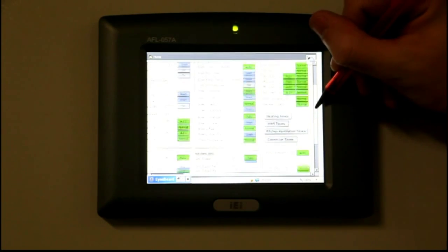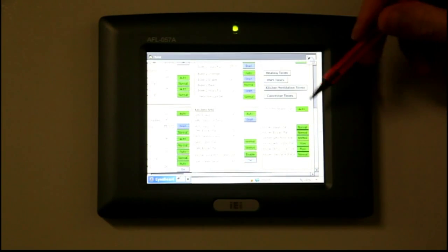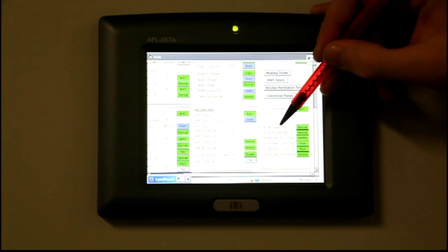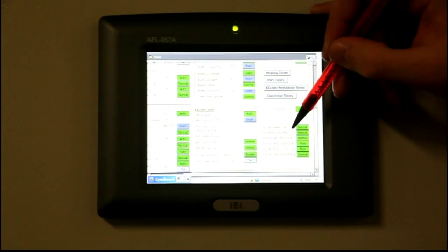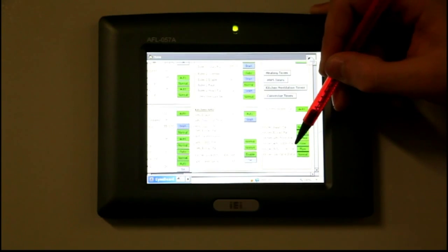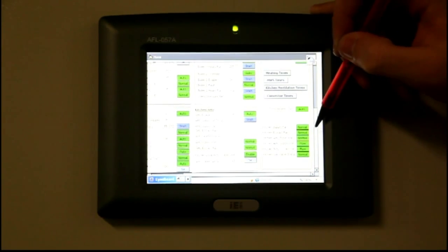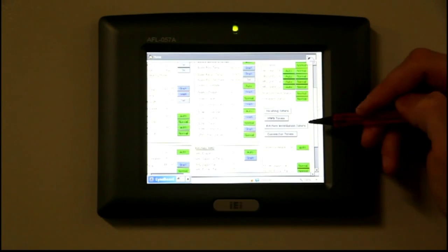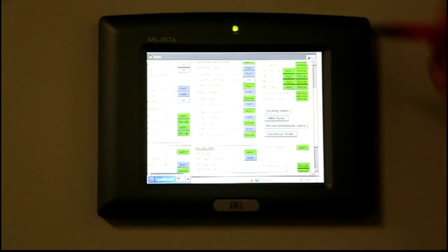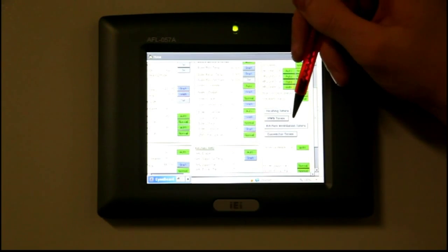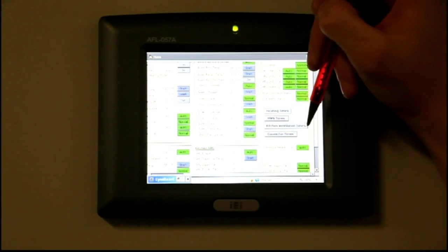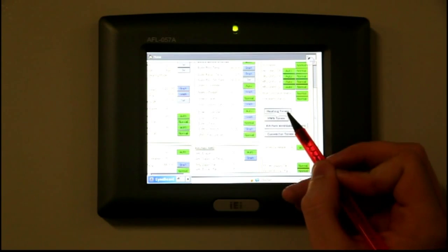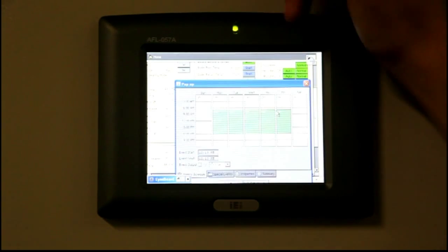At the bottom, we've then got the convector heater, whether that's in auto or off, and then all the stuff to do with the kitchen, so the supply fan, extract fan, thermostat, and the indications of whether they're in alarm or in normal operation. What we've also got in this third column is the times. The times can be adjusted for heating, HWS, kitchen ventilation or convector. To change the times, it will be a case of just clicking on heating times. That then brings up a pop-up screen.